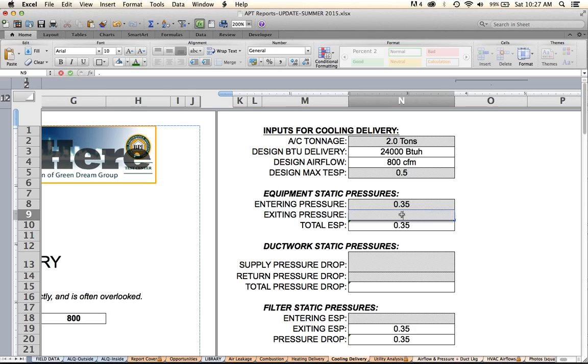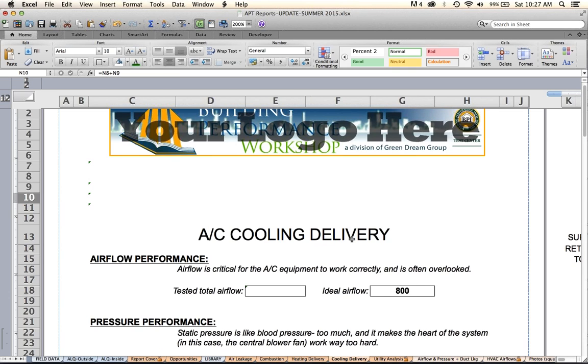The exiting pressure is the pressure after the heat exchanger of my furnace. And if I only have an air conditioning unit, then I don't have to worry about the heat exchanger, and it's after the coil, basically. External static pressure means all of the external stuff aside from the equipment. So that's what we're measuring right now. So the exiting pressure, you may have to drill a hole. In fact, in general, you do. You're going to have to drill a hole in the furnace. It's going to be at the top of the furnace, right before the coil of the air conditioner. So I'm going to make up an exiting static pressure of 0.25. We'll do that. And I've got a total external static pressure of 0.6.